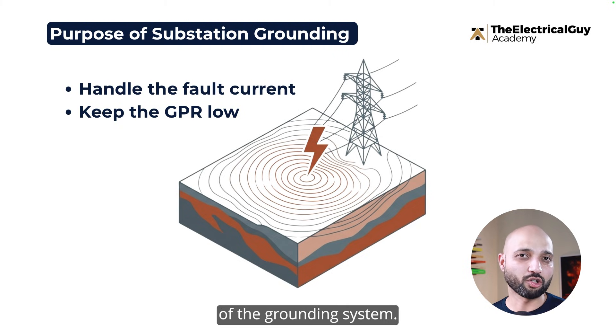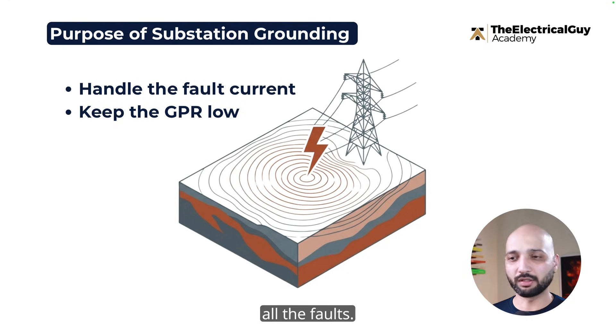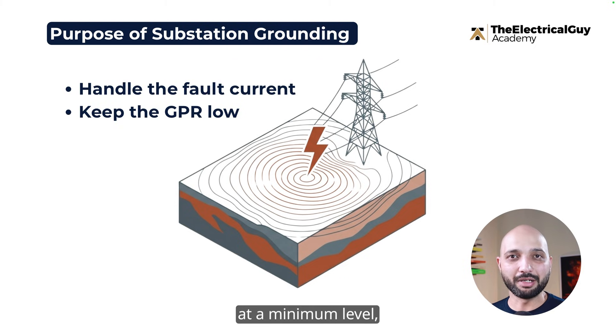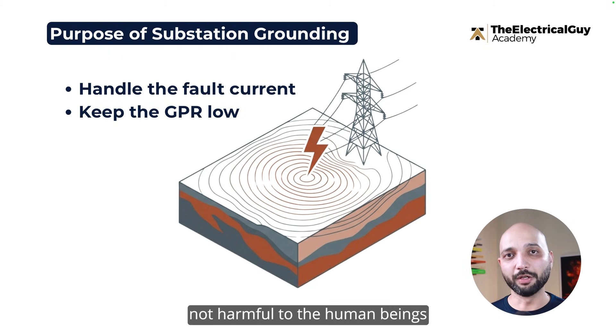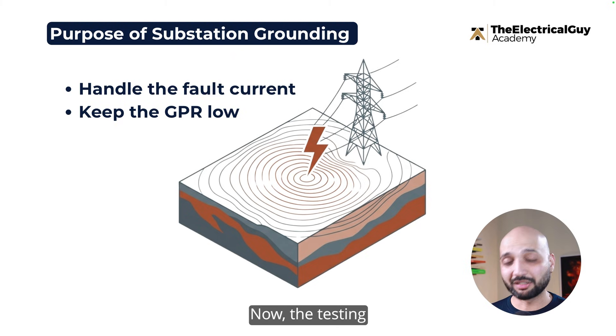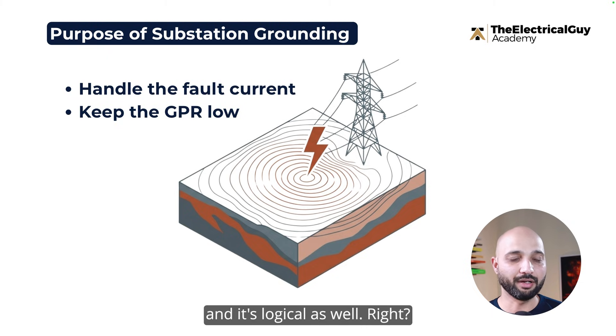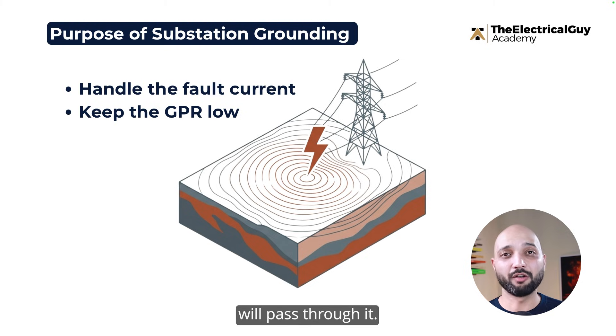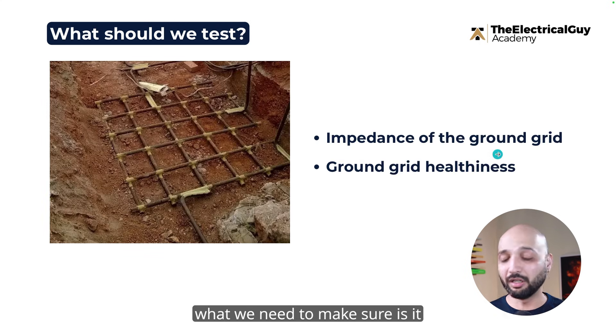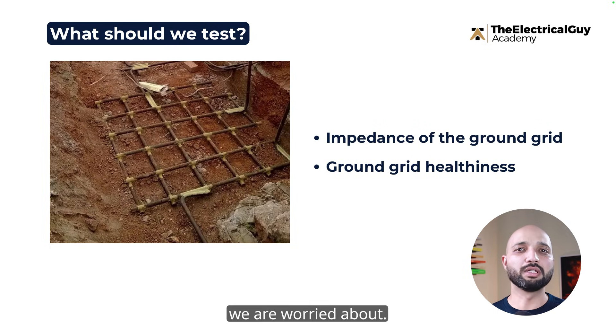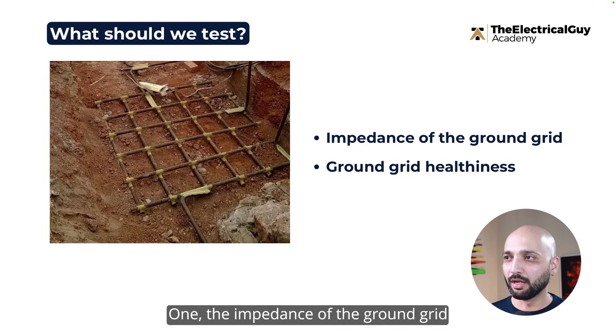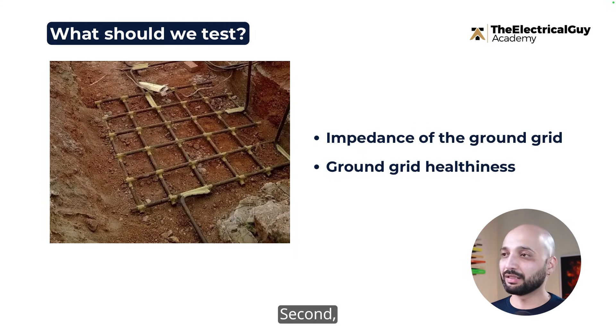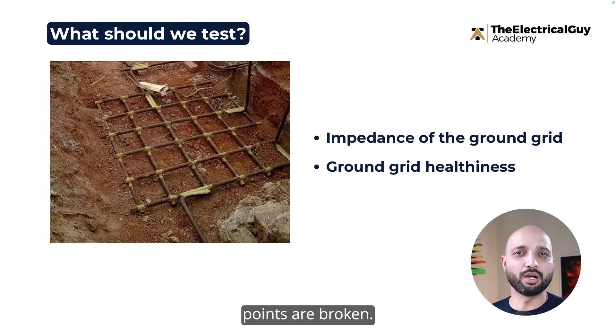The second purpose is that it should keep the ground potential rise, or GPR, under a certain limit. If it's not under the limit, we will have step and touch potential which is dangerous for living beings. So these are the two major purposes: first, it should divert ground faults; second, it should keep the ground potential rise at a minimum level — a level accepted by the standard and not harmful to human beings.